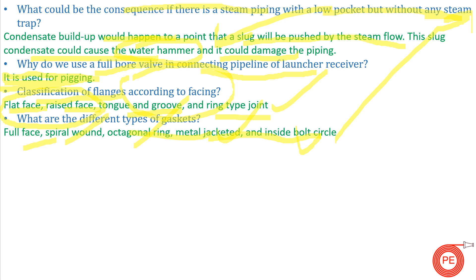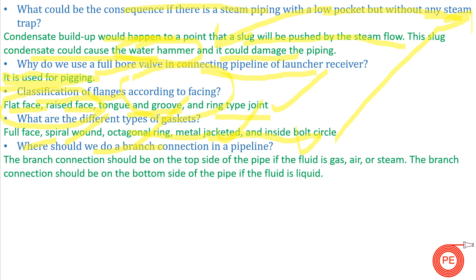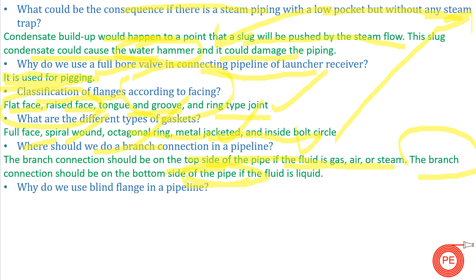Next question: where should we make a branch connection? If the fluid flowing through the pipe is gas, air, or steam, the branch connection is given on the top side of the pipeline. If the fluid is water or any liquid, the branch connection is done at the bottom side of the pipe.